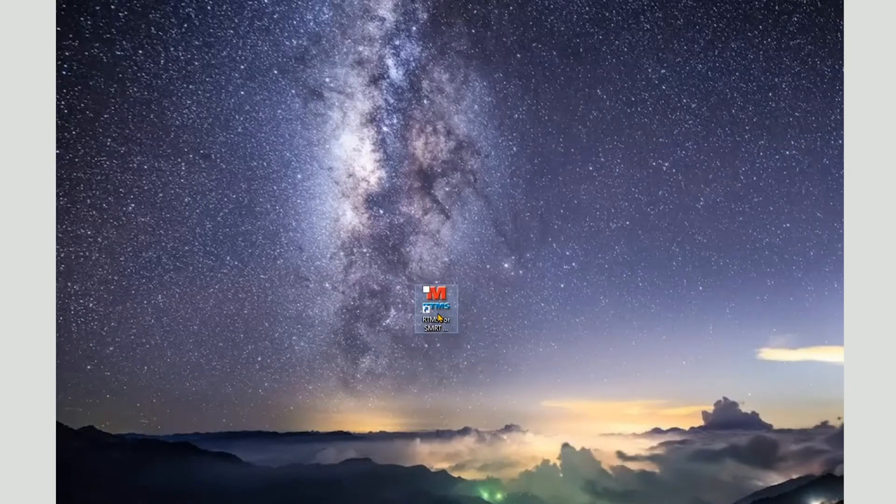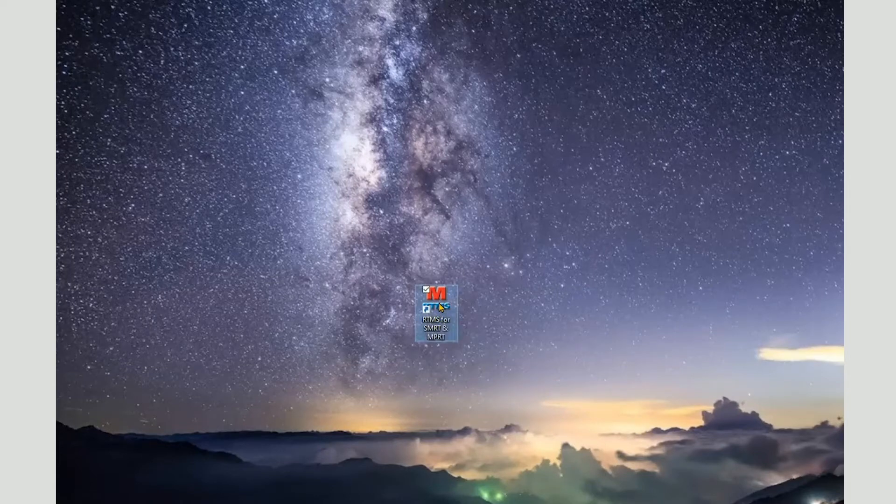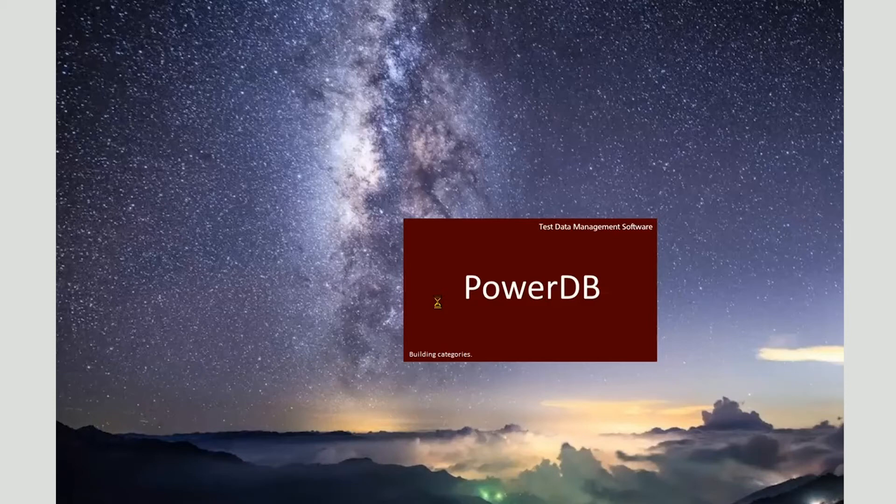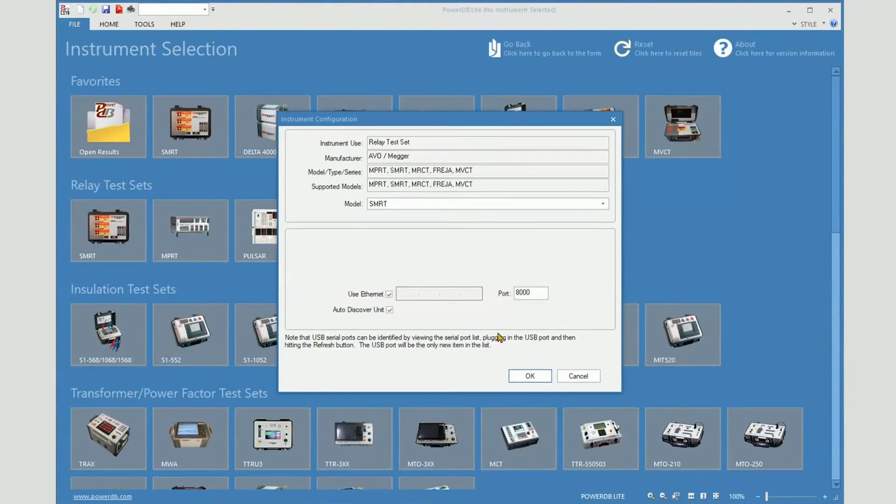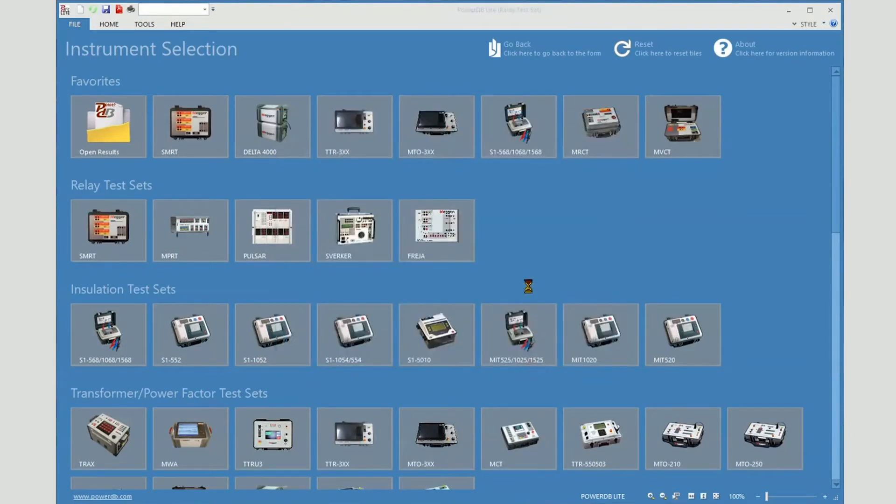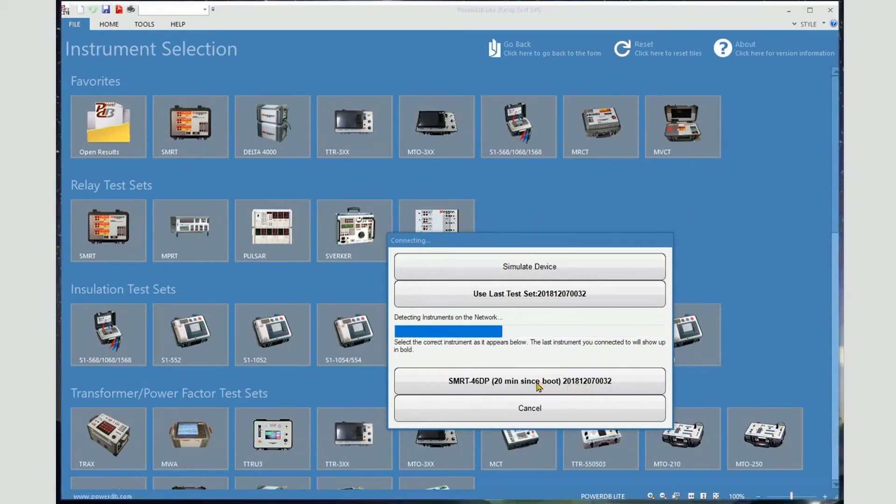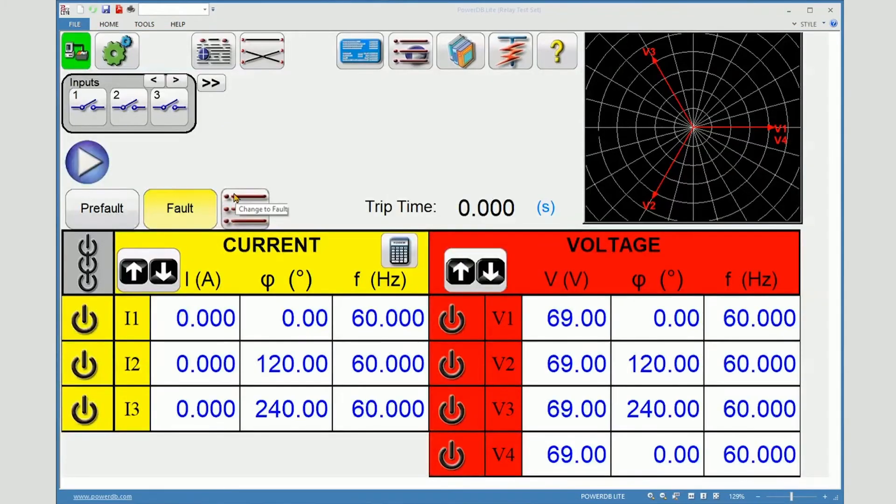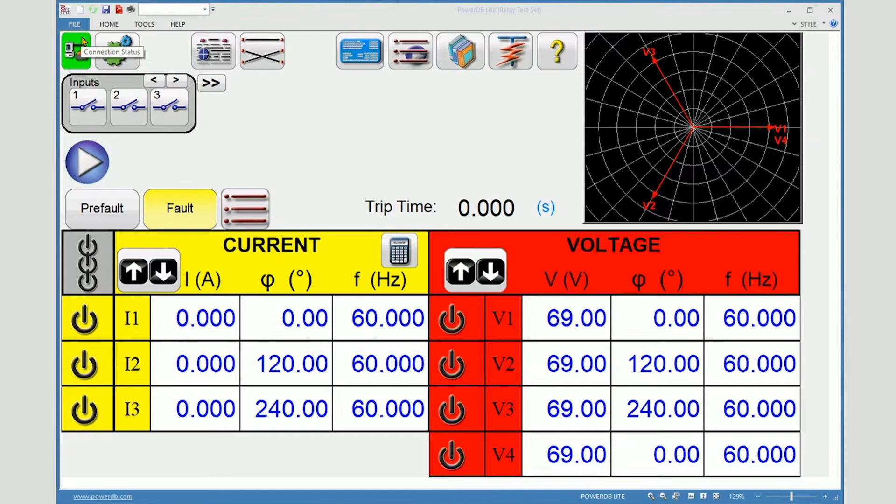Okay, I've reconnected by Ethernet, so I'm going to reopen RTMS from the RTMS icon. By doing this, it saves the step of selecting the instrument. Select Ethernet and connect. This is the unit I'm currently communicating with. Select it. And we are connected, as you can see once again by the green icon. It would be yellow if we were in simulate mode.